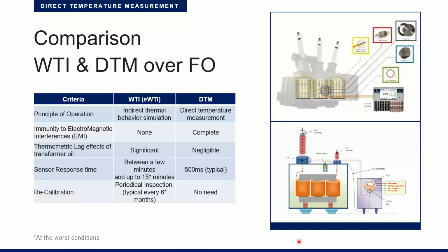So imagine you have to drive your transformers to the temperature limits. It's nearly impossible with the winding temperature indicator. It's not accurate enough, and it has very long response times. But you can do it with a direct temperature monitor. Let's just assume the sun is shining, the wind is blowing, and you ask yourself the question, what do I do with my transformer? It's loaded at more than 100%. Do I throttle it and lose money, or do I let it run and risk the destruction of my transformer?